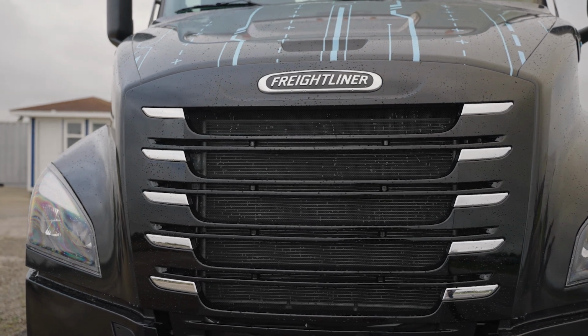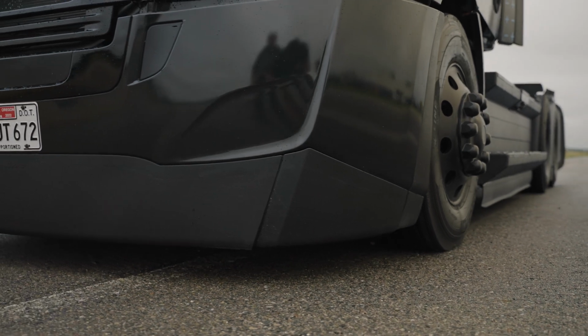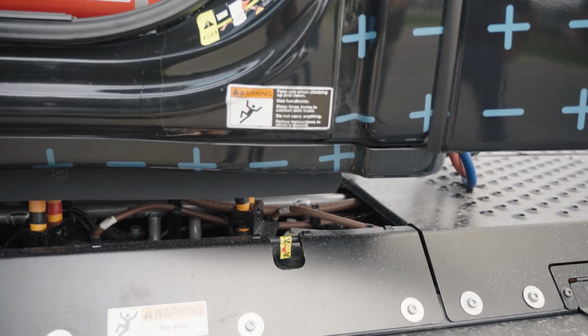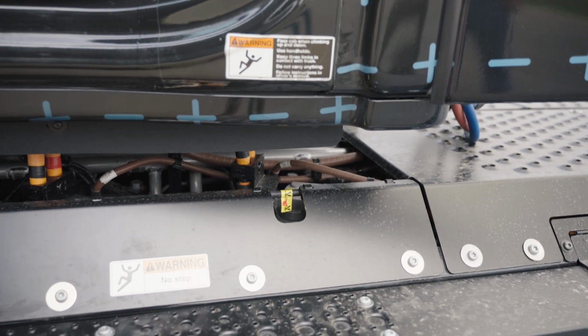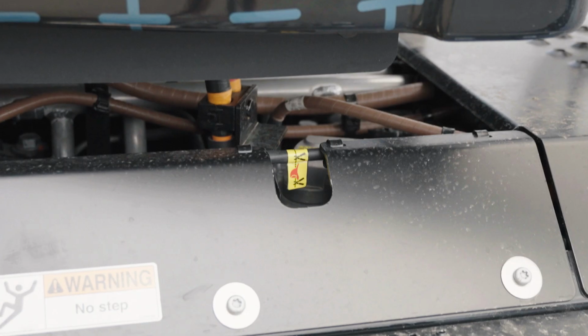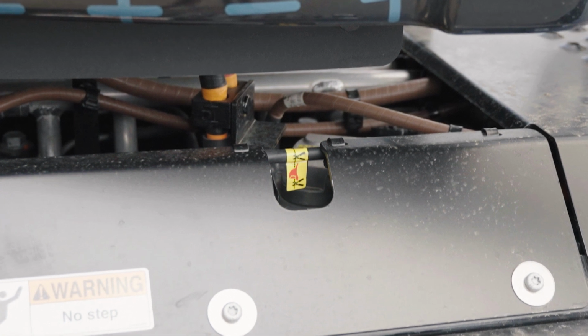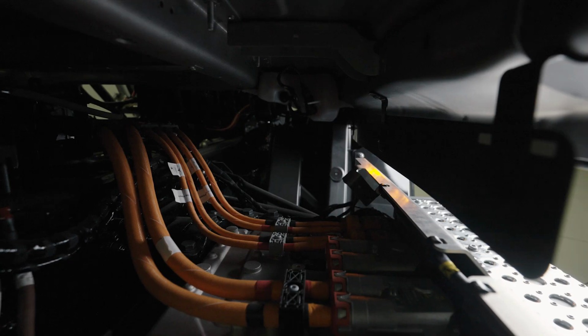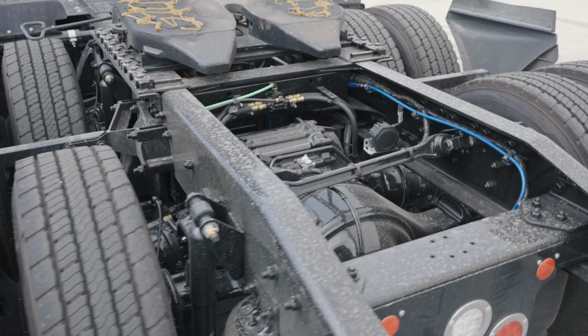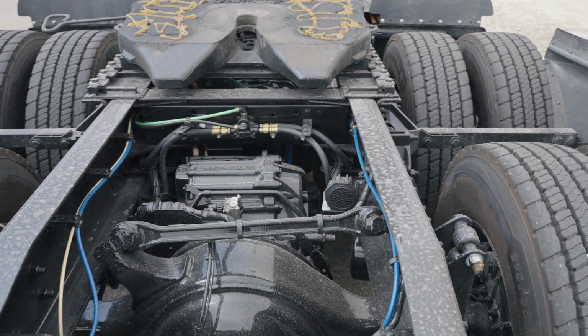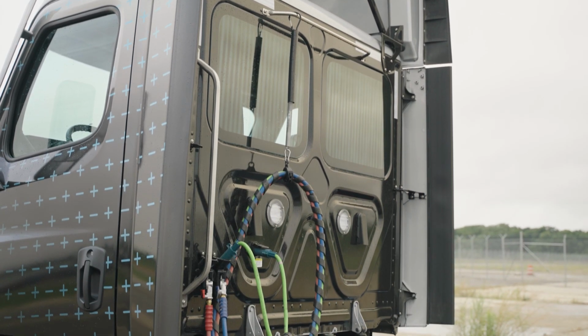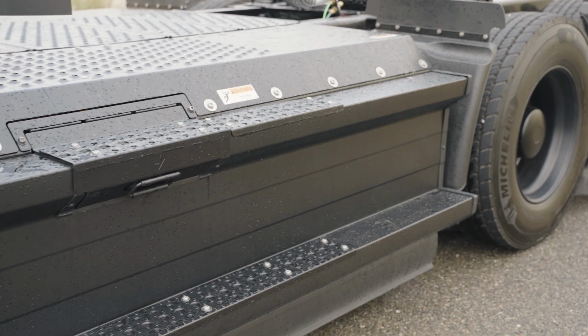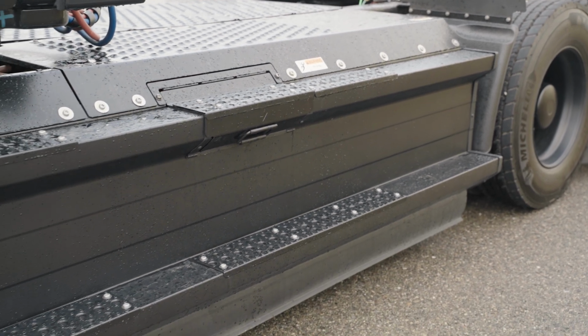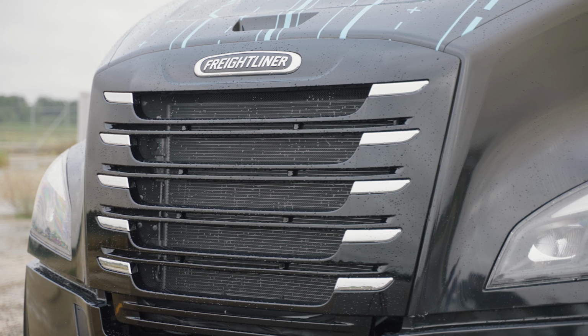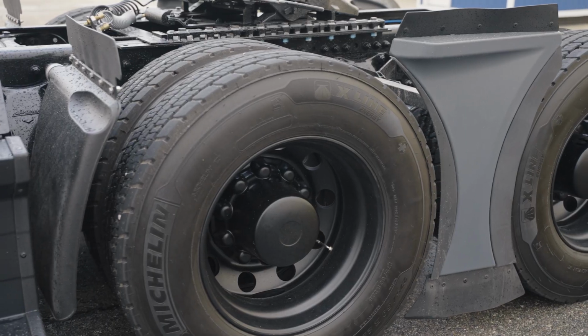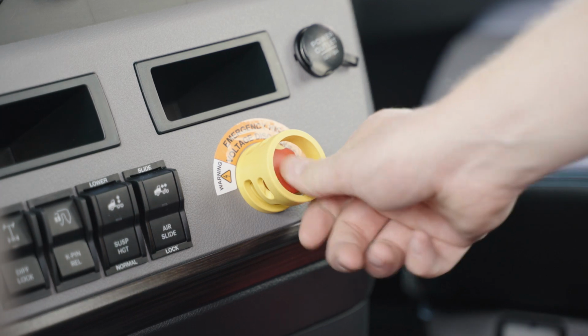The eCascadia is also equipped with an easily accessible emergency high-voltage cutoff point just under the cab and above the HV battery packs on the driver and passenger side of the vehicle. Like the e-stop button, cutting this cable will open the electrical circuit for the high-voltage system, shutting down the batteries and e-axles to help avoid any risk of electric shock or thermal events. The high-voltage system of the eCascadia is isolated from the chassis, and when undamaged, the system will not energize the surrounding water, even when fully submerged. Emergency personnel will check for damage and will disable the high-voltage system after removing the vehicle from the water.